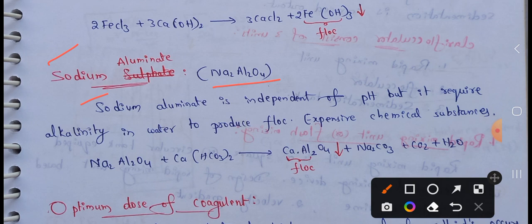Sodium Aluminate is independent of pH — it works across a wide range of pH values. It requires alkalinity in water to produce floc. However, this is an expensive chemical substance. That is why the alum method, which is cheaper and effective, is generally preferred.